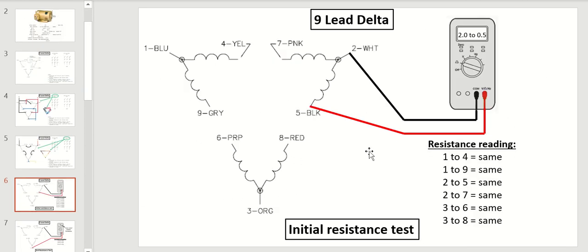When it comes to doing resistance testing on the 9-lead delta motor, the first thing you want to test is to make sure that all of the windings have the same internal resistance. It's just a coil of wire wrapped around an iron core, but the resistance should be the same on all of them. It's important to disconnect all of the wire connections. You never want to condemn a motor until you've absolutely tested to make sure that you know there's something wrong with it, and this is how you would do that with a digital multimeter. Make sure that each one of these windings measures the exact same resistance or fairly close to the same resistance.